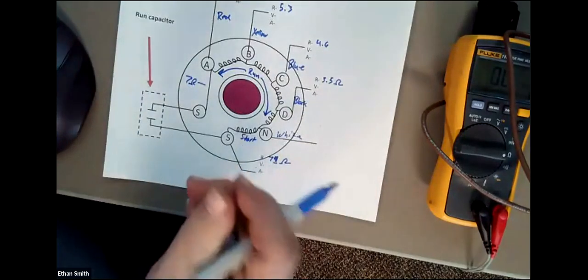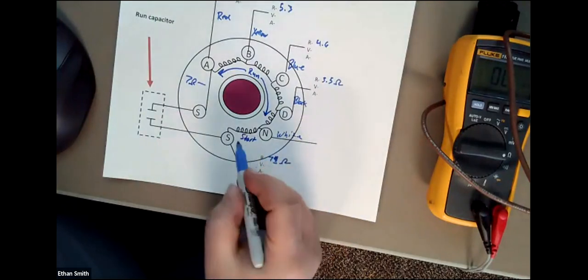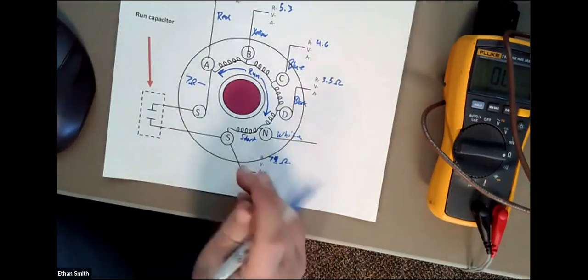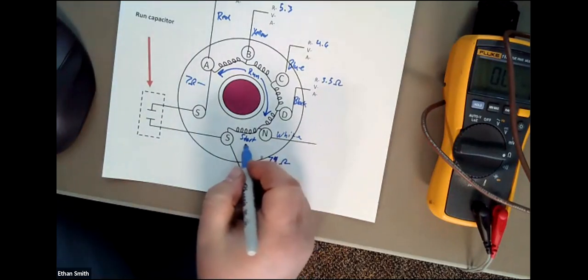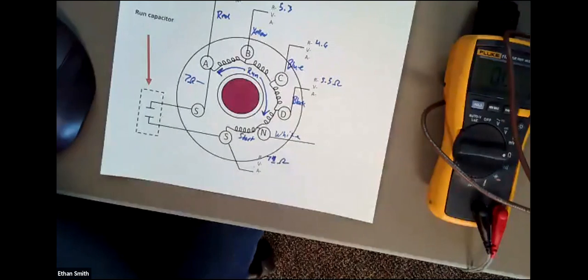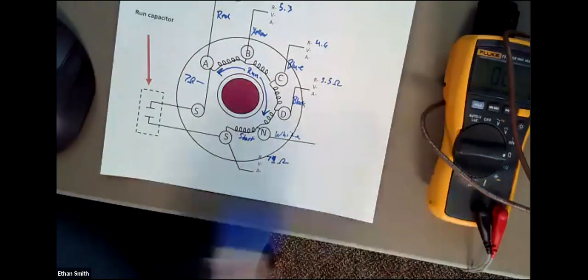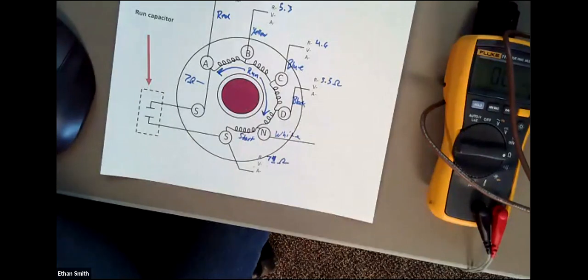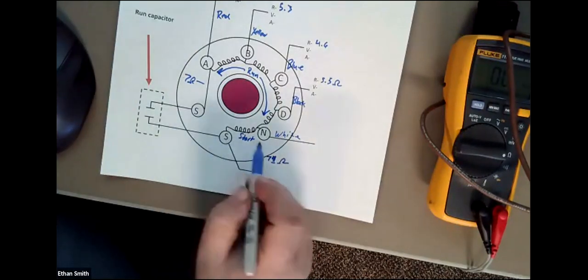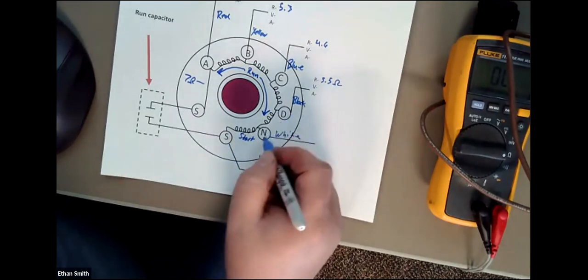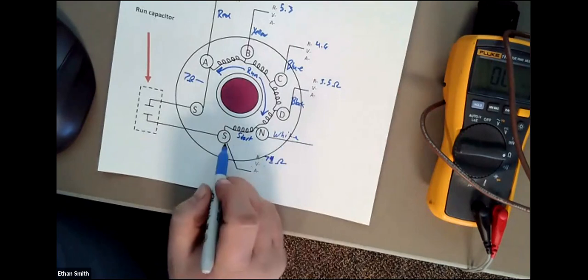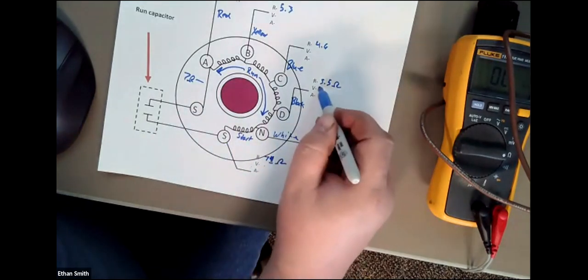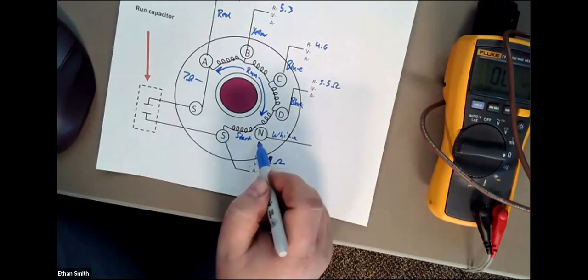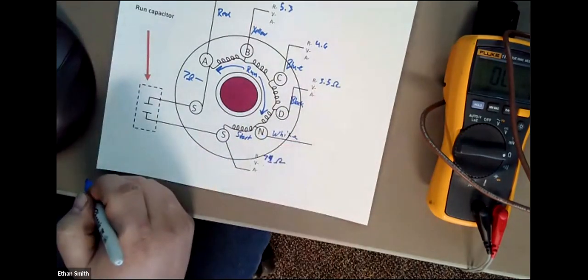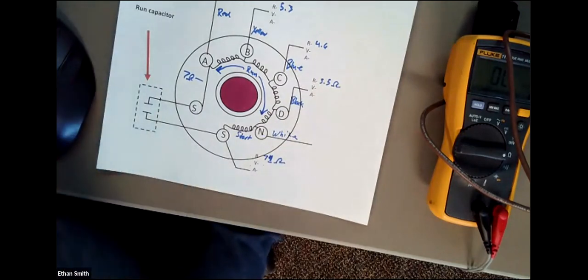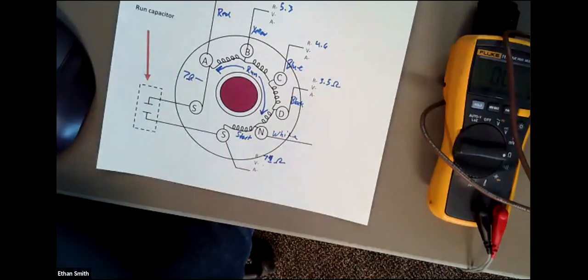Okay, so that start winding is, remember, that thinner gauge wire, and it's a lot longer. So a combination of the length of the wire and the gauge of the wire makes that resistance higher. So that's how you can tell which one is your start wire, where your start winding is. So that also tells you where your neutral is too, because your neutral is going to be between the smallest and the largest ohm readings you get. That's your neutral terminal. Okay, make sense? Everybody on the same page? Any questions?